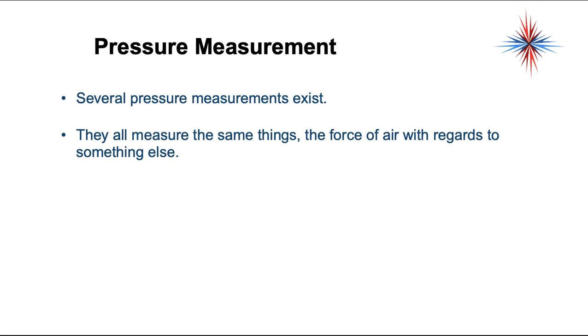Let's talk about pressure measurements, because if you don't measure, you don't know. Several pressure measurements exist, and they all measure the same thing: the force of air with regards to something else. We work on differentials. The pressure in a building is measured with regards to the pressure outside the building. The pressure in ductwork is compared to the pressure in the building, and so on. You always measure pressure in one area with regards to pressure in something else.